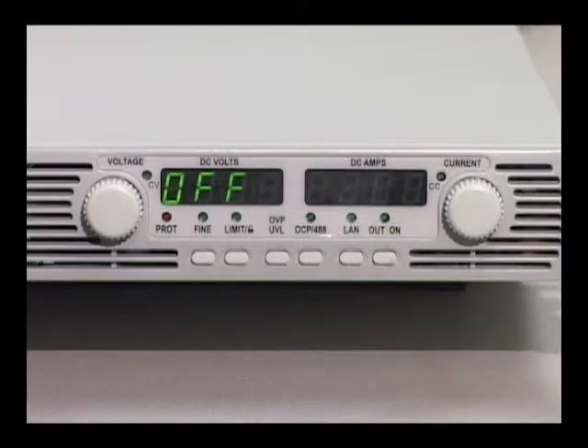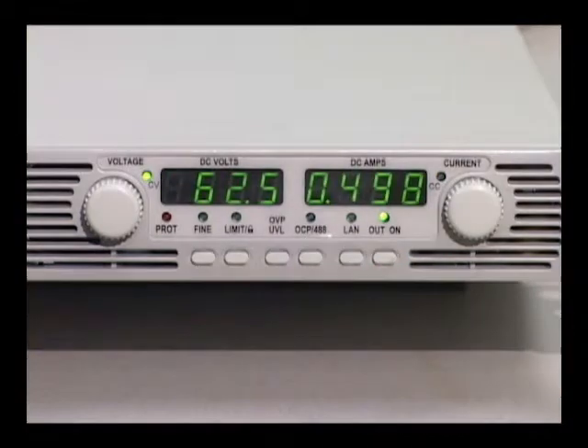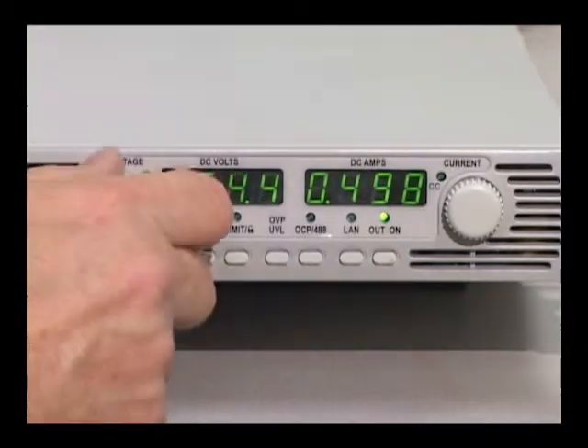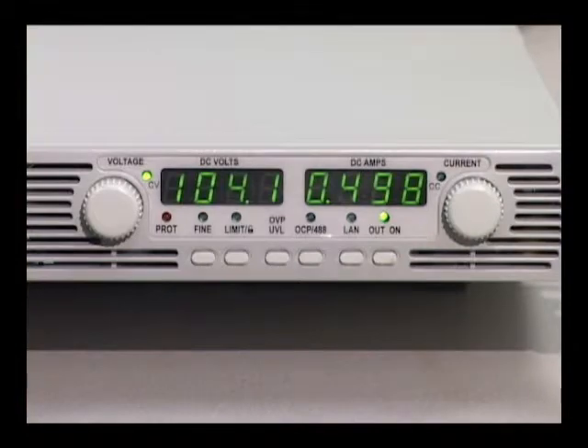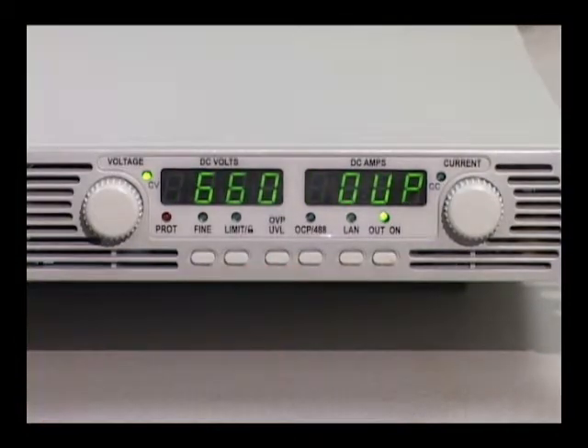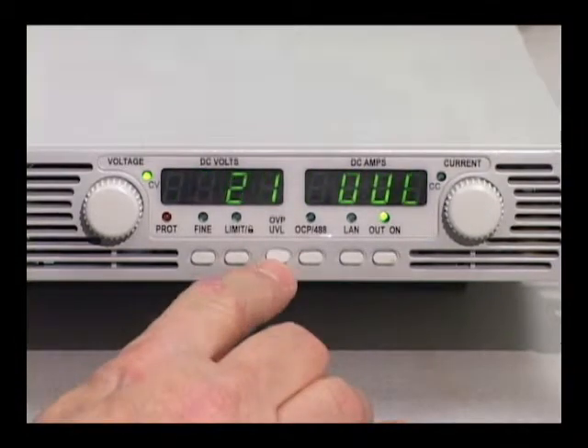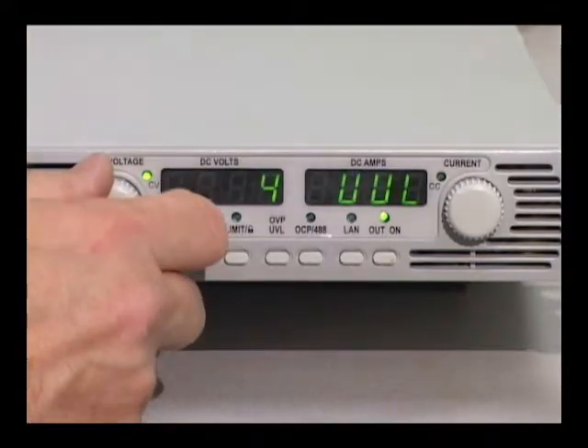Using the front panel controls you can adjust the output voltage and current, specify protection settings and select power on recovery states. To protect against accidentally changing settings you can remotely lock out the front panel controls.